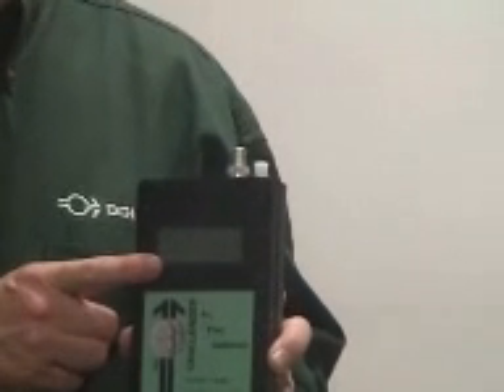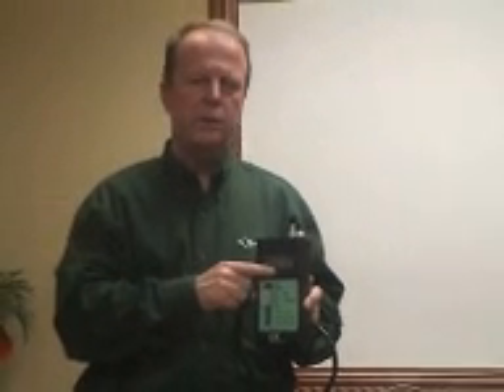The display gives you all the information. It gives you the ambient temperature, the barometric pressure, QA, which is flow actual, and QS, flow standard. It tells you the strength of your battery, so that if your battery is starting to wear down, it'll give you a signal. And in addition, it has an RS-232 connection.